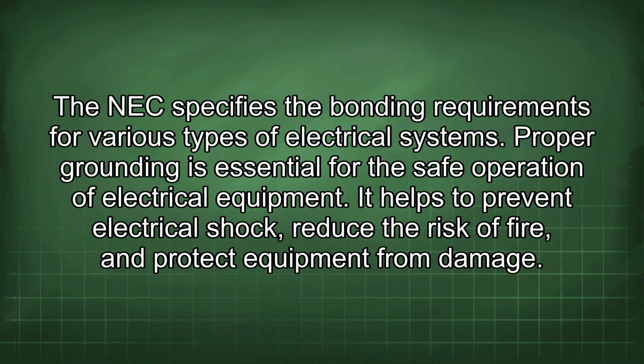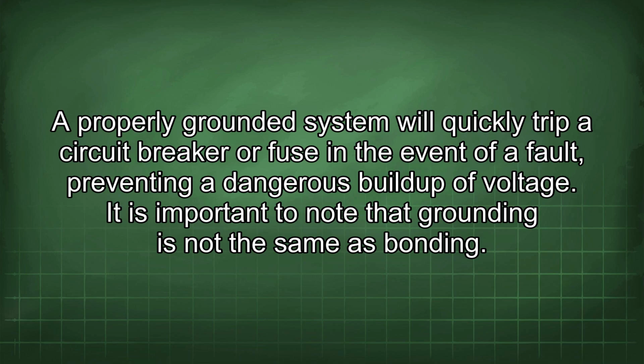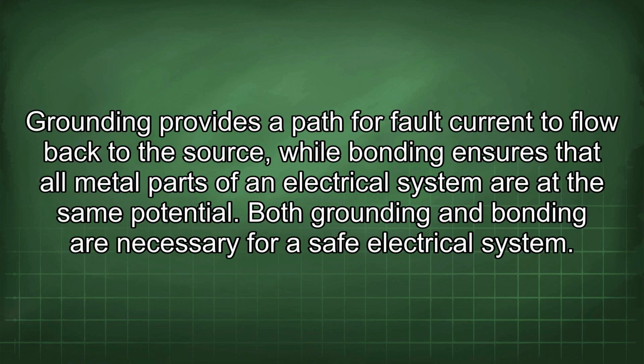Proper grounding is essential for the safe operation of electrical equipment. It helps to prevent electrical shock, reduce the risk of fire, and protect equipment from damage. A properly grounded system will quickly trip a circuit breaker or fuse in the event of a fault, preventing a dangerous buildup of voltage. It is important to note that grounding is not the same as bonding. Grounding provides a path for fault current to flow back to the source, while bonding ensures that all metal parts of an electrical system are at the same potential. Both grounding and bonding are necessary for a safe electrical system.